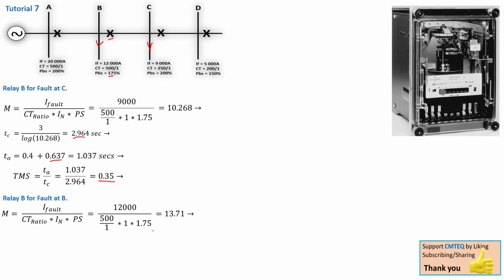Remember, the same relay settings are left unchanged here. The only thing that changed is the fault current, because we are now working on bus bar B. We can then go ahead and replace it into the TC formula. That is 3 over log of 13.71, and that gives us a value of 2.64 seconds. Now we've got the value of TC, we can go ahead and calculate the value of TA, the actual time.